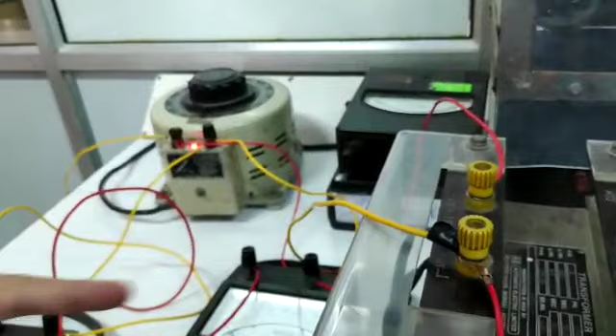Now we are going to start the voltage ratio test. In this test we have to connect a single phase transformer and 3 voltmeters. Voltmeter 1 is connected in the primary, voltmeter 2 in the secondary, and V3 between the common points of the first and second voltmeter.